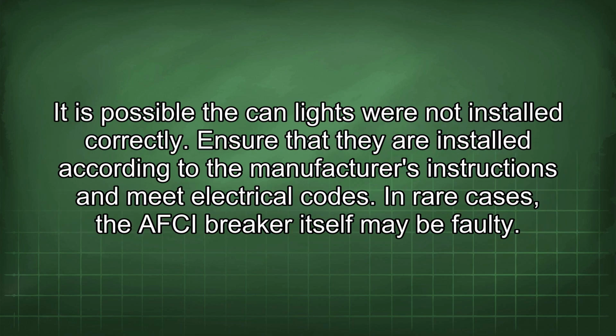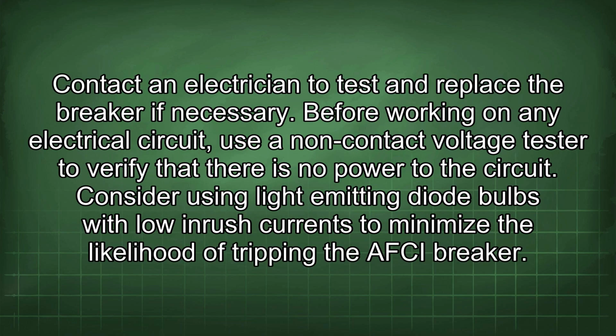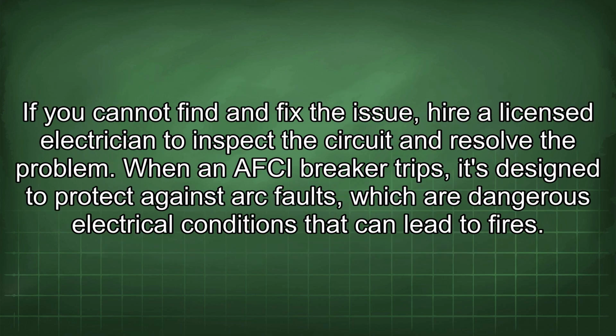It is possible the can lights were not installed correctly. Ensure that they are installed according to the manufacturer's instructions and meet electrical codes. In rare cases, the AFCI breaker itself may be faulty. Contact an electrician to test and replace the breaker if necessary. Before working on any electrical circuit, use a non-contact voltage tester to verify that there is no power to the circuit. Consider using light-emitting diode bulbs with low inrush currents to minimize the likelihood of tripping the AFCI breaker. If you cannot find and fix the issue, hire a licensed electrician to inspect the circuit and resolve the problem.